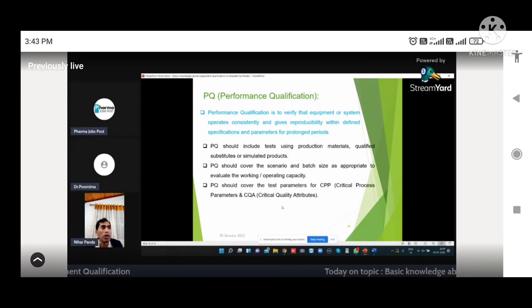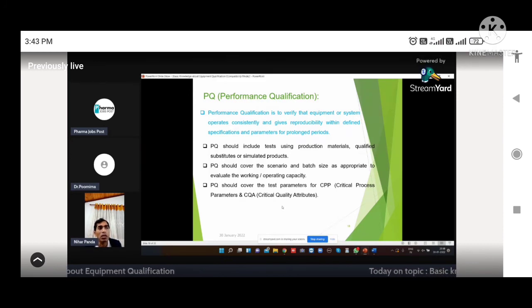Then PQ, performance qualification. Performance qualification is to verify that the equipment or system operates consistently and gives reproducibility with defined specification and parameters for a prolonged period. During PQ, this is the main part, and the protocol and report are to be prepared by the user department. Most of the manufacturers are not providing the PQ part. Few companies are providing the PQ part, but most equipment manufacturers are not.